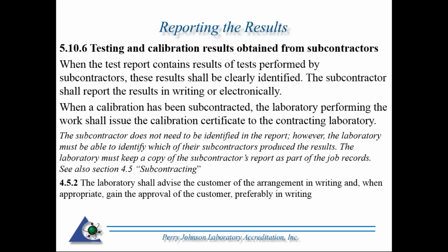Where appropriate, the approval needs to be granted. Again, if you're providing the reports, the results shall be clearly identified. So if your reports contain the results of subcontractors, those results need to be specified within the calibration reports that you're issuing to your customers.